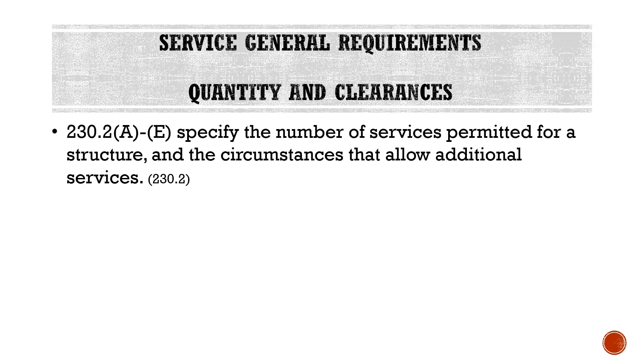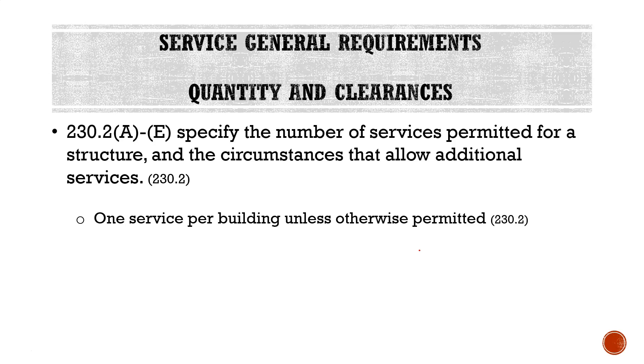Looking at our service general requirements, we have quantity and clearances. Section 230.2A through E specifies the number of services permitted for a structure and the circumstances that allow additional services — one service per building, unless otherwise permitted. Unless we have a special rule or exception, we're allowed one service entrance per building. There are a variety of circumstances that allow you to have more than that, but that is the general rule.